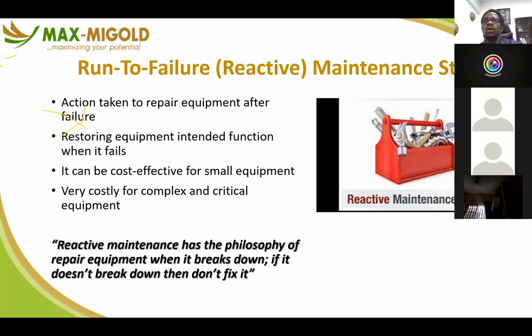So you let them be and only monitor them for when faults arise, and then you fix them. It also helps to handle situations where you have redundancies. If I have 2 or 3 pumps, for example, all networked into the same water production system in my facility, such that only one pump works at a time, when that pump fails, I can change the valve directions and activate the next pump and take the first pump out for repair. I don't need to put any kind of maintenance in place for any of the pumps because I have N+1, N+2, which means first level redundancy, second level redundancy for that particular asset.